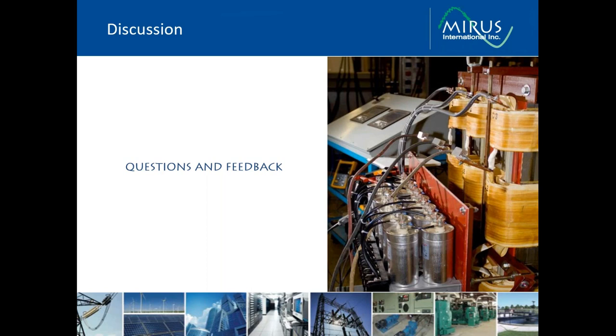The next question is about diagnostics. I guess in a situation where our filter had an experience of failure or any kind of over temp condition, are there any internal diagnostics that can be done to tell us of those conditions? Absolutely. We've developed an optional meter that can be ordered with the filters. This meter will monitor our capacitors, monitor the temperature in our reactors. It can also be connected on the input of the filter and do full power monitoring.